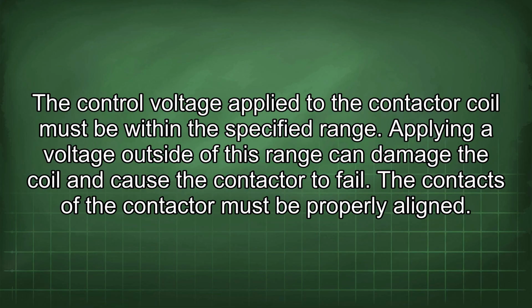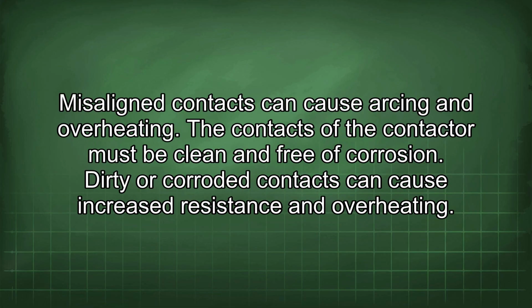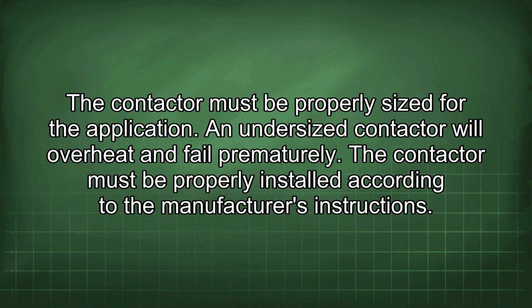The contacts of the contactor must be properly aligned. Misaligned contacts can cause arcing and overheating. The contacts of the contactor must be clean and free of corrosion. Dirty or corroded contacts can cause increased resistance and overheating. The contactor must be properly sized for the application. An undersized contactor will overheat and fail prematurely.